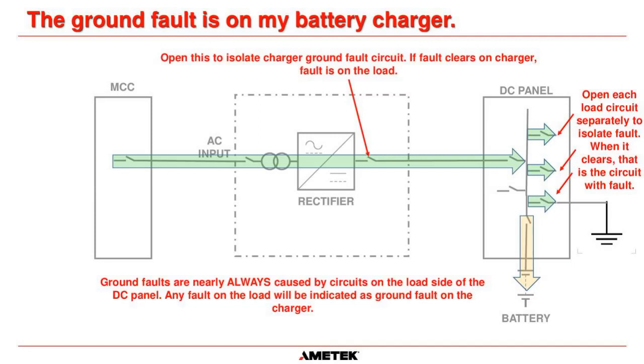And then, unfortunately, what you need to do is go out to each individual load circuit and open each one until the LED or lamp on the charger goes off. There is another way. You can use a ground fault detector. Basically what that does is you connect a signal generator to the pole that has the fault. So let's say on this one, it's a positive. So you connect one lead to the positive and then one lead to ground. It sends a signal only through the positive ground circuit. And then you get sensors, basically transducers that you can put around each cable. So you could put it around this cable. And if it says that there's a ground fault, then you move to each individual circuit, and then it will show you which of these circuits specifically has a ground fault on it. It's a very good piece of equipment to find ground faults.